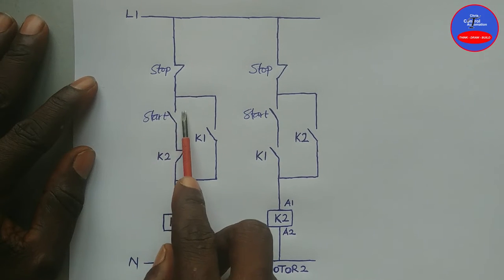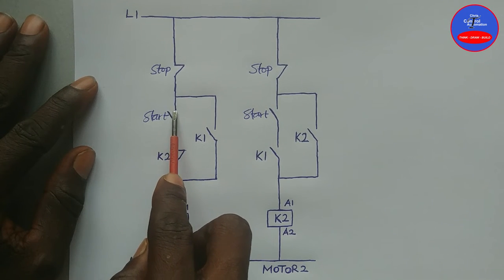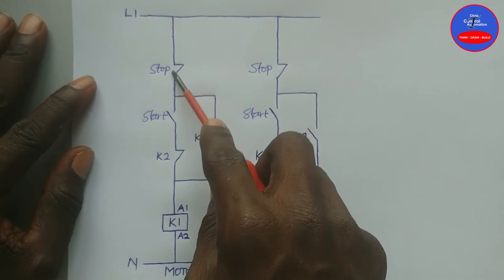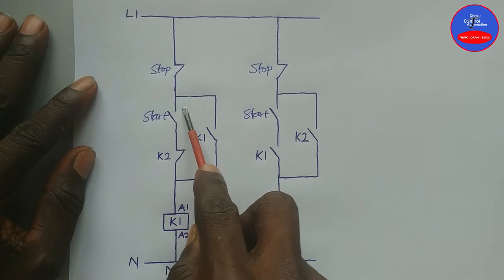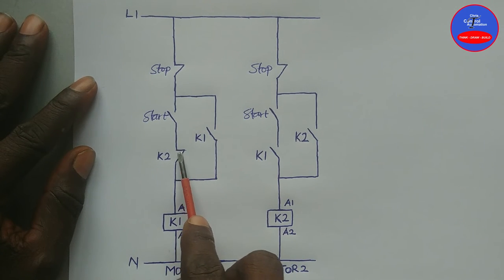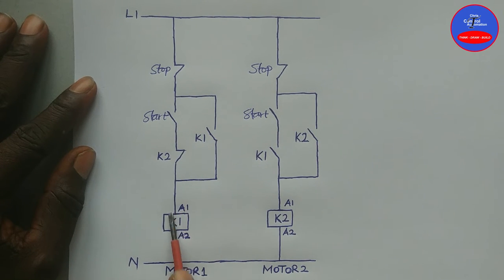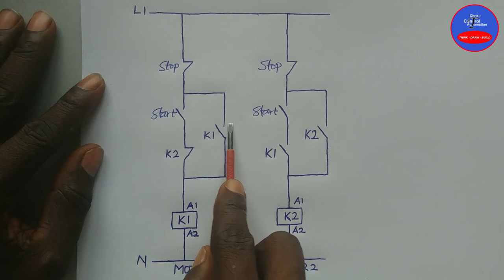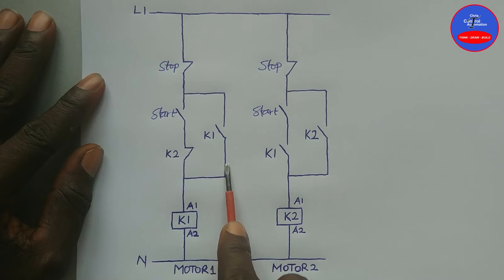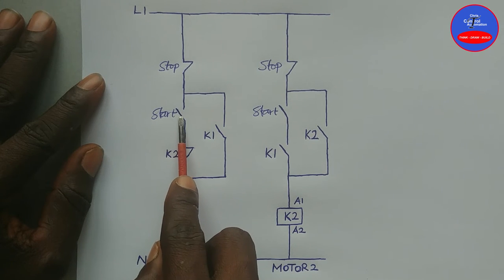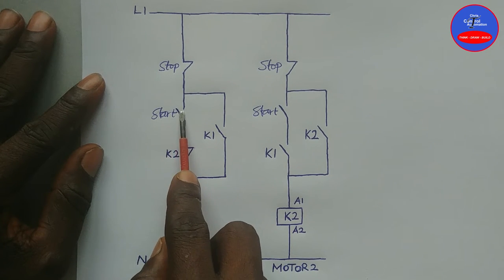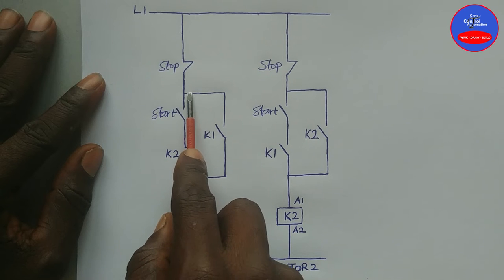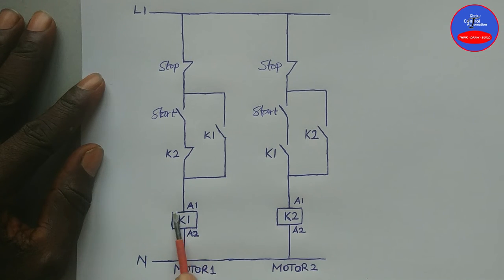Now let me come back to Motor 1's circuit. When you press on the start button it becomes closed, therefore current can flow through this close contact, through this close contact, through this close contact on Contactor 2 to energize Contactor 1. When Contactor 1 energizes, this open contact will close to serve as a hold-on, so that when we remove our hand from the start button and it opens, current can still flow through this close contact on K1 to maintain K1 in the energized state.